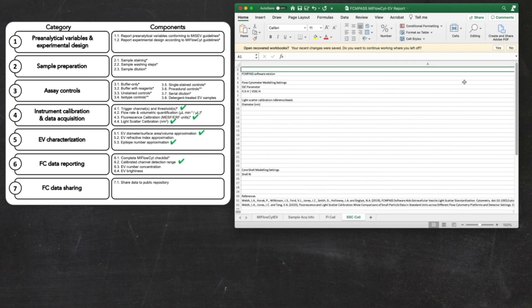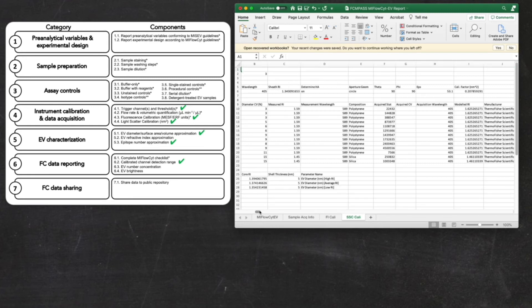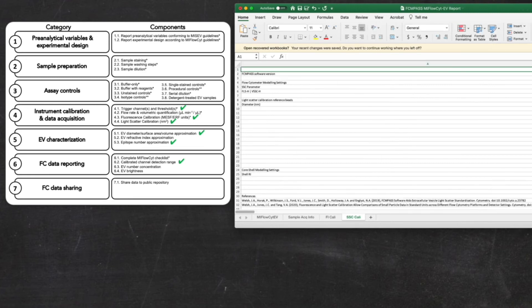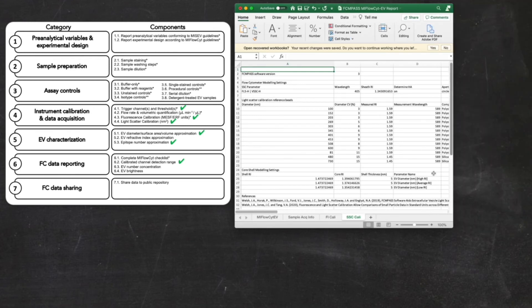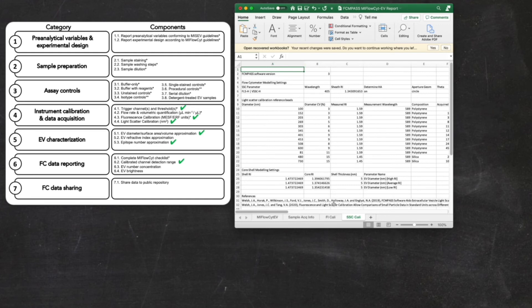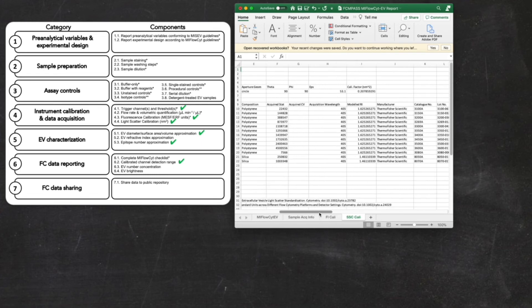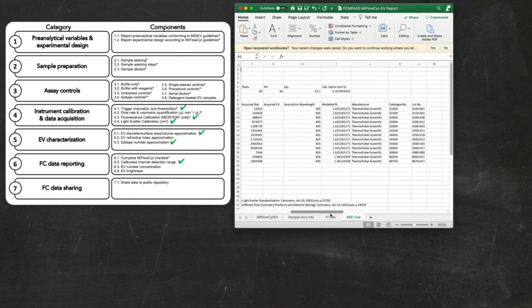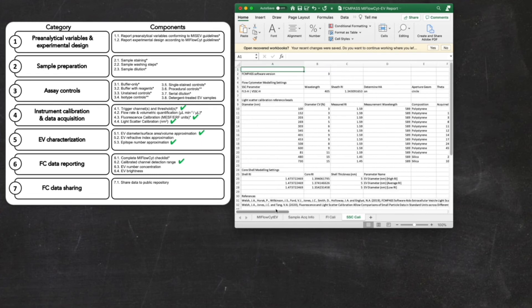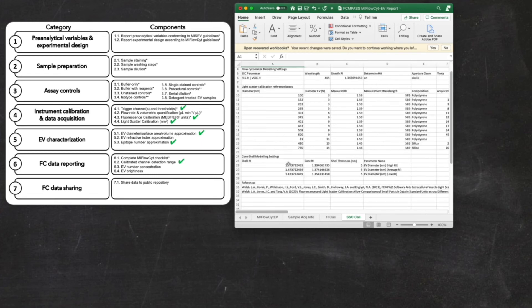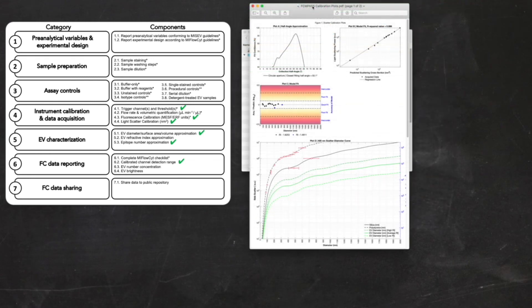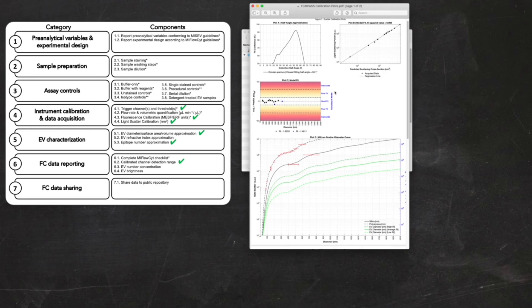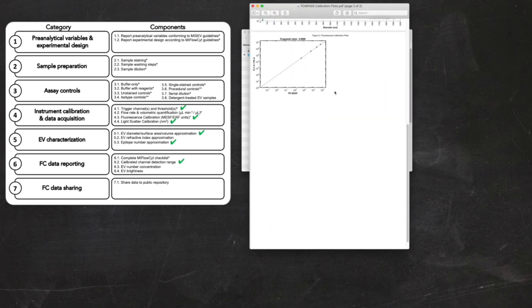This table just needs reformatting slightly if we make this first column smaller. But this table essentially, again, has all of the metadata associated with the model that was just generated. So we have all of the bead information in there, the refractive indices of the beads, the catalog numbers, the acquisition statistics, and everything else that you'd need to know to reproduce this model if you didn't have the FCS files. So the last output we'll look at is the quality control plots. The first page has the light scatter calibration model fits and your scatter diameter curve there down at the bottom. And the second page contains your fluorescence calibration plots. This will just be a page full of the fluorescence regressions.